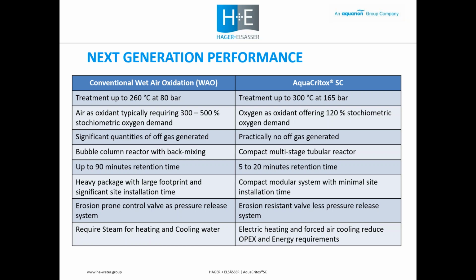With the tubular reactor, we have a lower retention time, 5 to 20 minutes, typically 12 for a standard system. A conventional wet air oxidation system would be using a pressure vessel kind of reactor. They would be employing up to 90 minutes of residence time. So not only is this a large vessel to start off with, the residence time required is even larger, and you end up with a very heavy, cumbersome unit, which also has back mixing, which isn't present in a tubular reactor. The overall package footprint and weight, therefore, of a wet air oxidation package is large. The AquaCritox system is compact and lighter and easily transportable as a complete package.